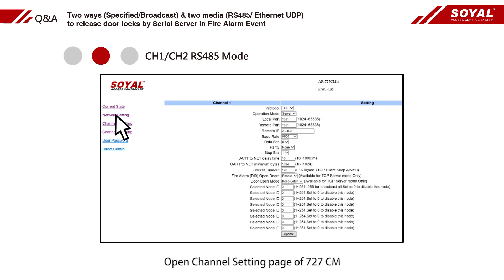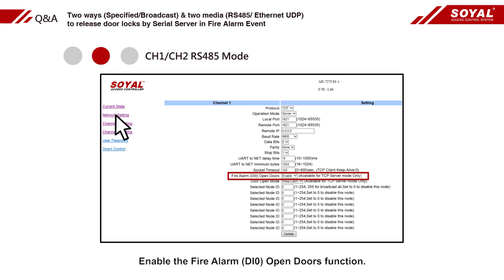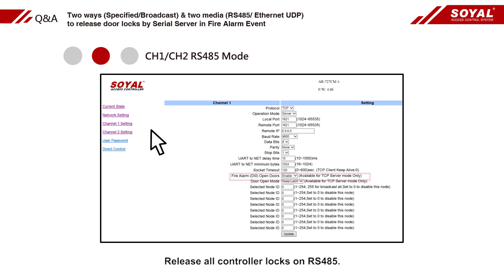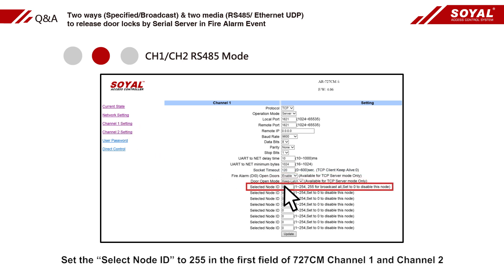Open the Channel Setting page of 727CM. Enable the fire alarm open door function to release all controller locks on RS-485. Set the select node ID to 255 in the first field of 727CM, channel 1 and channel 2.